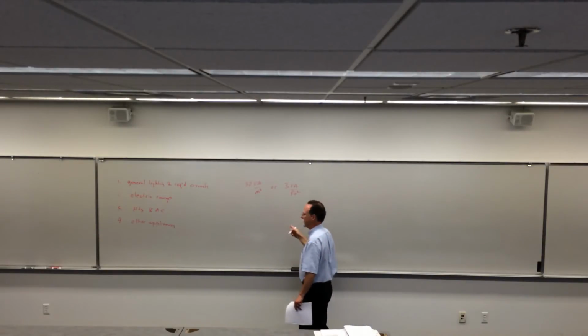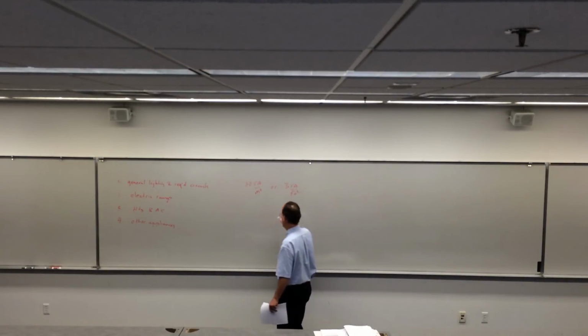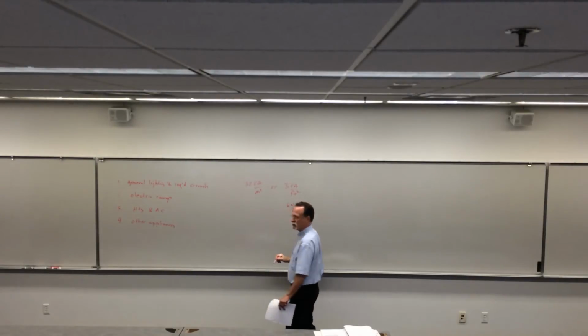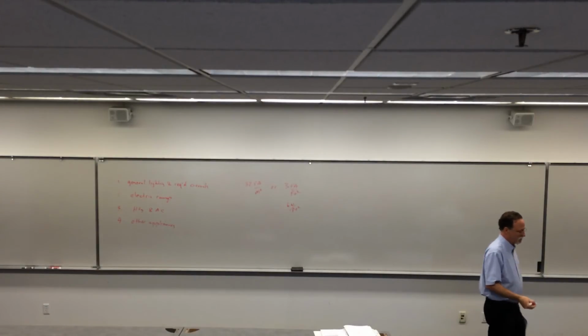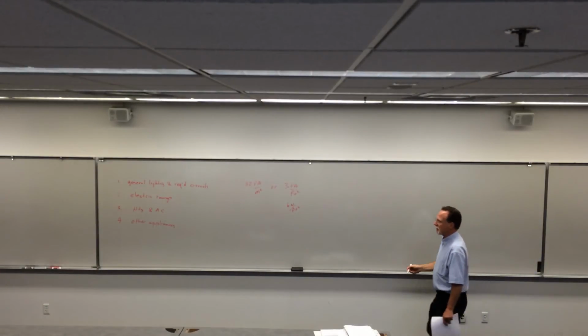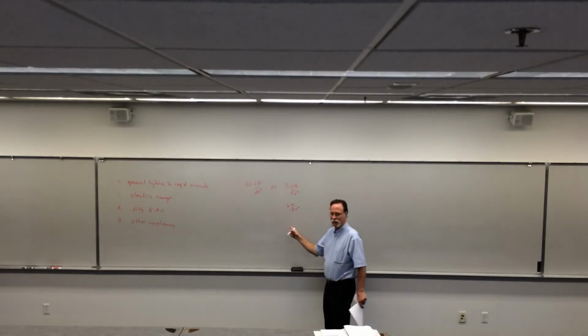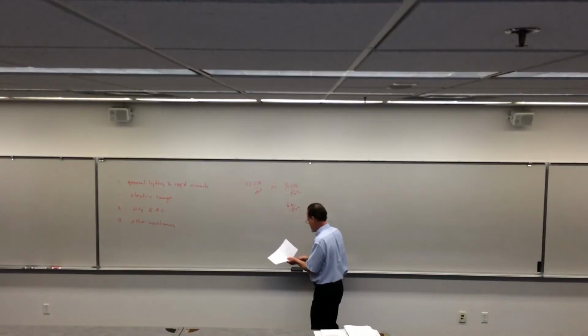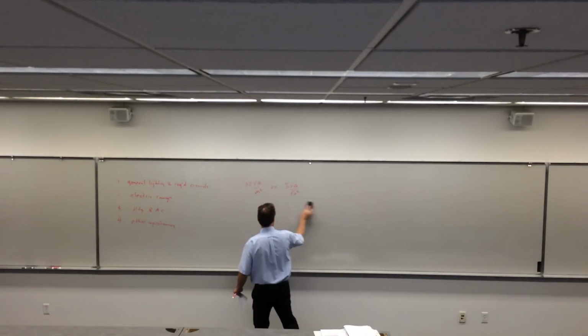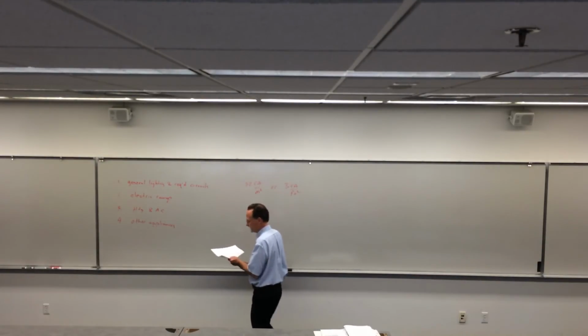Now, think about that. If I put LEDs in there, I could put in 0.6 watts per square foot. Big difference. So we haven't swallowed that change yet in the way we write our codes. Because somebody could come back in and put the other lights in there, and you want your circuitry and your system to be able to handle it. So that's the difference on that. And I'll erase that before we go much further.